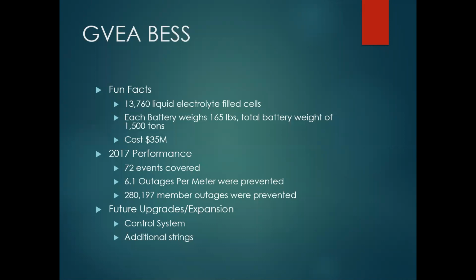When you're talking about these 72 events, would some of those involve frequency regulation and voltage regulation only, not necessarily a direct short, but within your 5% plus or minus? So basically you're firming up the grid to keep it maintained at 60 hertz. Would that be typical coverage for the battery, or is it more like, there's a short, we replace the power with this? No, some of those events are frequency disturbances caused by, say, loss of generation outside our service area, Anchorage. You're stabilizing the grid.